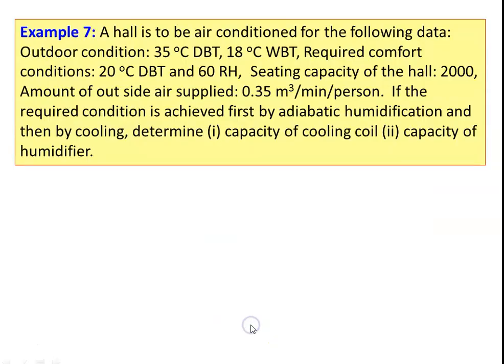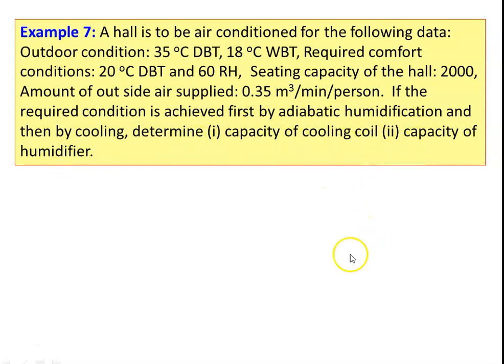Example number 7: a hall to be air conditioned with outdoor conditions 35 degree Celsius dry bulb temperature and 18 degree Celsius wet bulb temperature. Required comfort condition: 20 degree Celsius dry bulb temperature and 60 percent relative humidity. Seating capacity is 2000, amount of outside air supplied is 0.35 cubic meter per minute per person. The required condition is achieved by adiabatic humidification and then cooling. Determine capacity of the cooling coil and capacity of the humidifier.